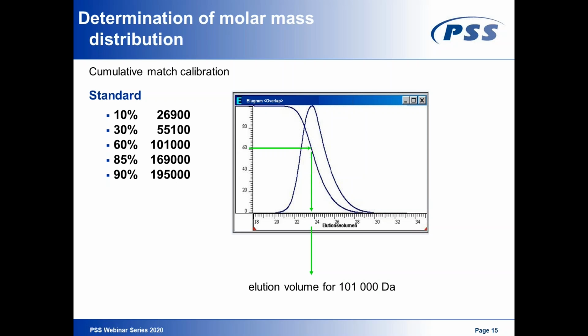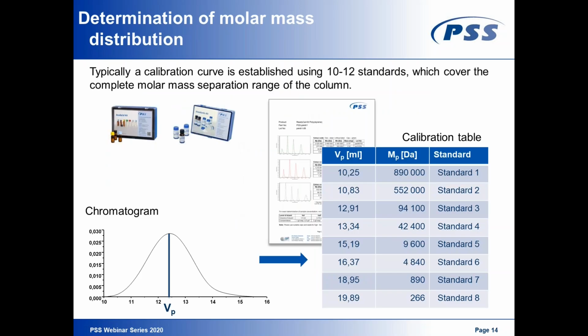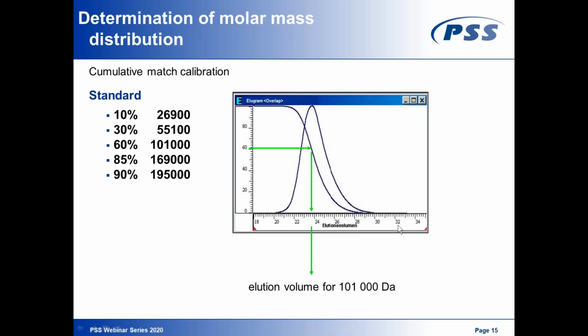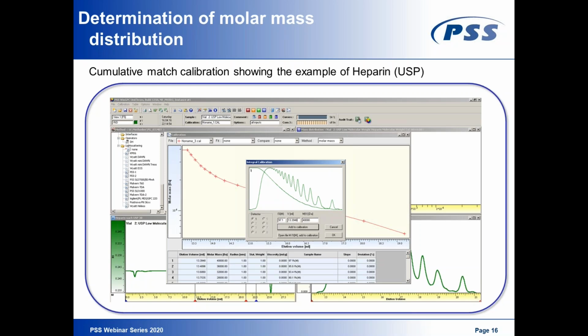So what you do is you measure this broad standard on your column set, on the column set you want to calibrate, and then you can just read from the integral curve here, the cumulative match curve here, at 60% the elution volume, and can assign that to the molar mass of your certificate, so that you will end up with a table like here, but much more detailed. I'll show it to you in an example with the heparin, with the USP standard. You see here in green the chromatogram, here the automatically determined curve of eluted mass, and then you can just assign all the different molecular weights reflecting the different parts of elution here, and have with one injection, with one standard, a calibration, a chemically matching calibration for your unknown heparins that you want to characterize.